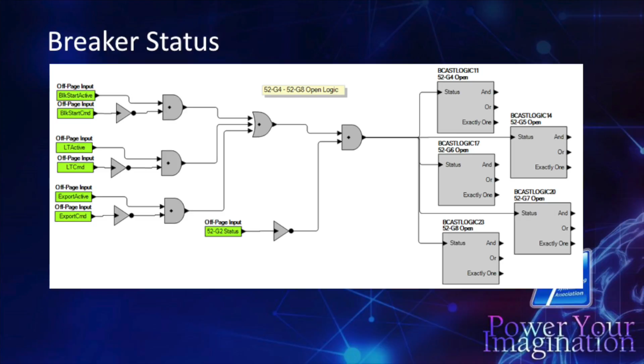So we ran into some issues immediately upon our first testing where the group breakers never opened because we shut the generators down first. So there was some back and forth figuring out what was going on. So we put time delays in the generator stop. They will not stop until all the group breakers open. And then they'll stop. That allows us to have that because the power for the breakers is on the generator side.